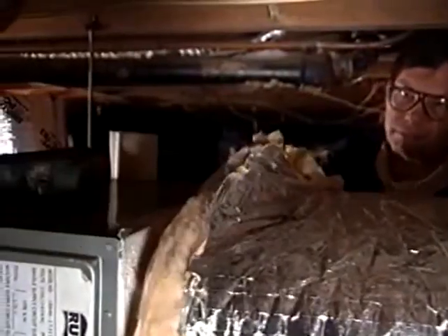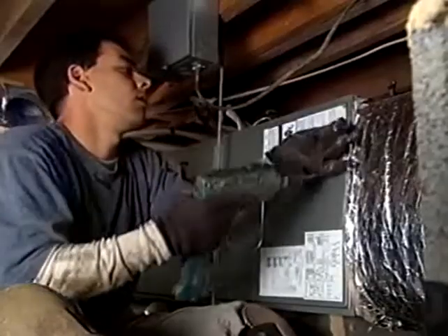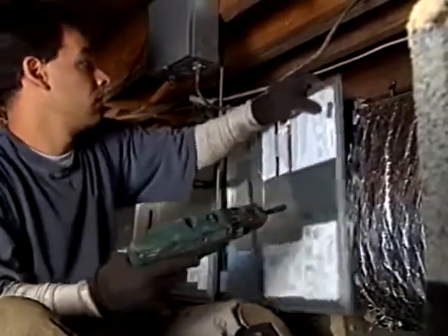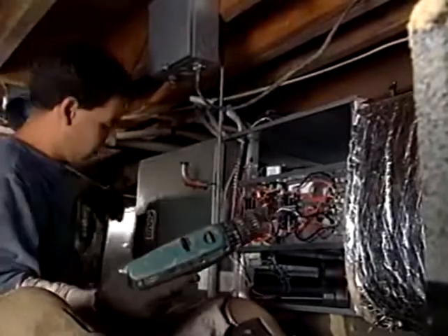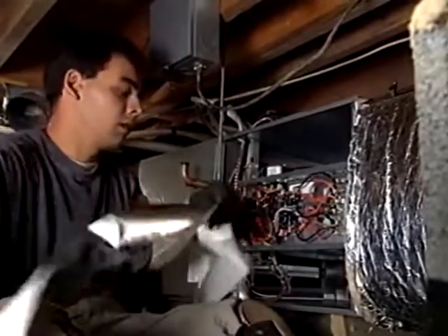After this connection is sealed, it's important to secure the insulation. This contractor holds the insulation in place with a UL 181 foil tape. About right there. Squish it in real good there. He takes the door of the air handler off, both to protect it and to make sure the seal isn't broken when opening this door in the future. As before, he uses fiberglass mesh tape around the entire connection and then seals it with mastic.